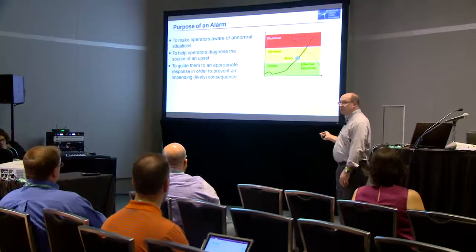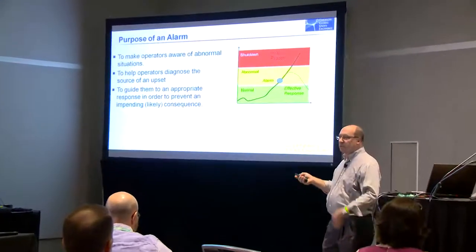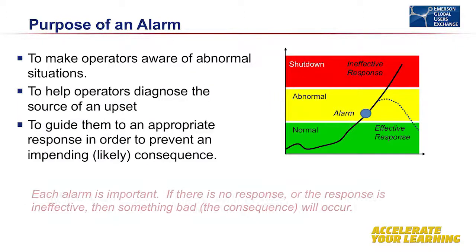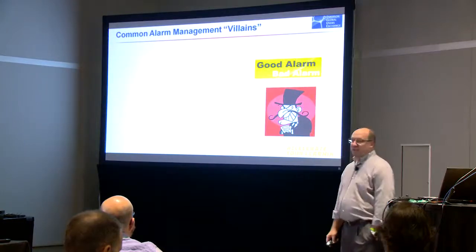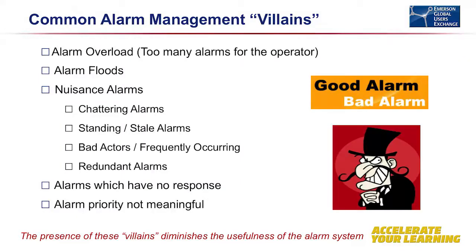However, if the operator doesn't respond, the process continues to deviate and we end up with either a consequence or a shutdown, which we want to try and avoid. So the whole idea is that when the alarm occurs, that means, Mr. Operator, you need to do something. You need to take a corrective action or else a consequence will occur. So it's a pretty simple concept. Unfortunately, in the real world, a lot of our alarm systems are not really set up to match that idea of what an alarm is supposed to be.